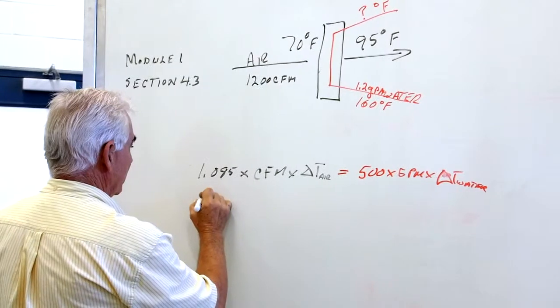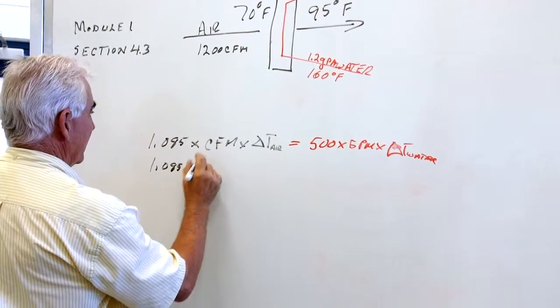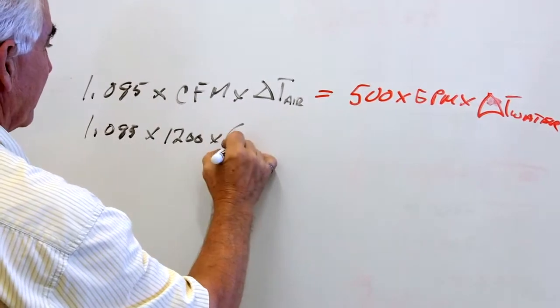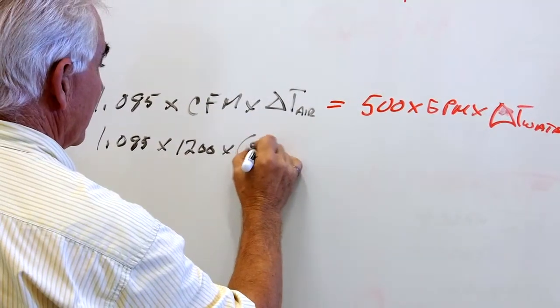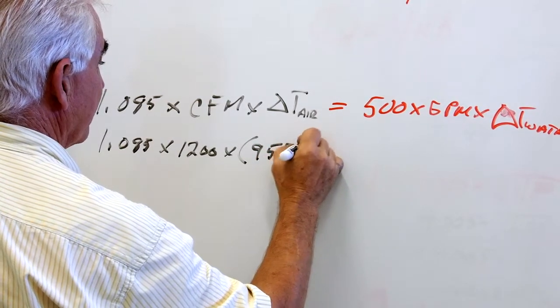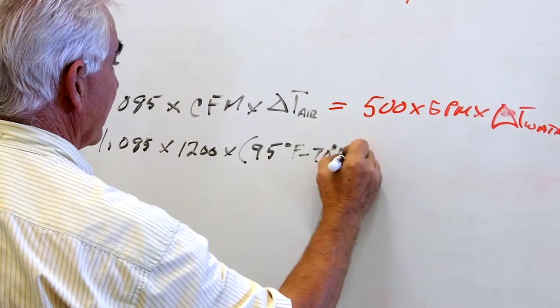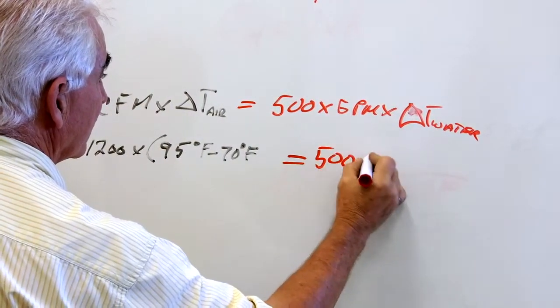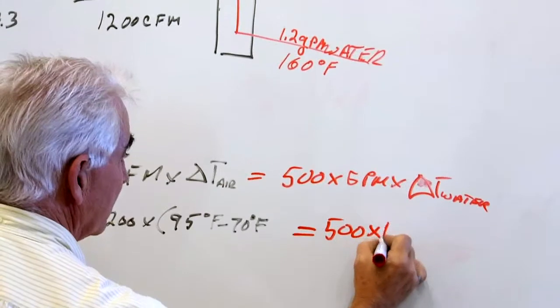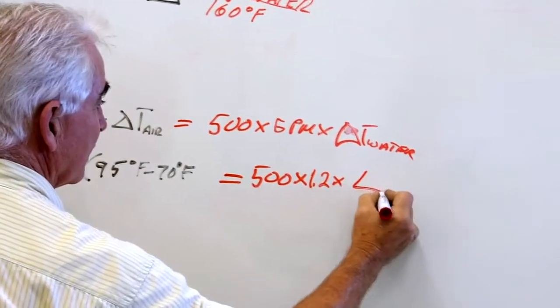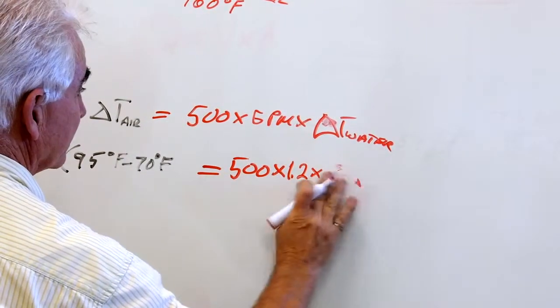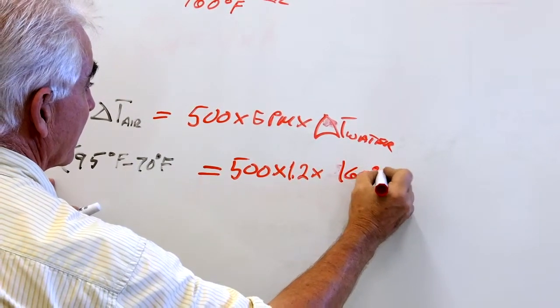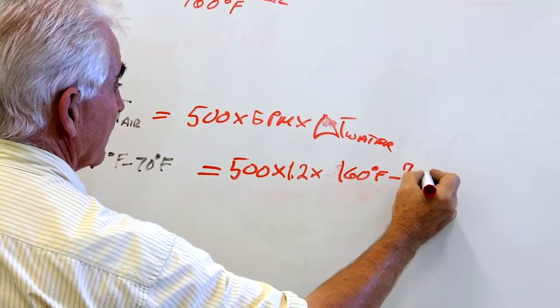So we'll have 1.085 times the CFM, which is 1200, times the delta T of the air, which is 95 degrees Fahrenheit minus 70 degrees Fahrenheit. That is equal to 500 times the GPM, which is 1.2, times the delta T of the water, which is 160 degrees Fahrenheit minus the unknown leaving water temperature.